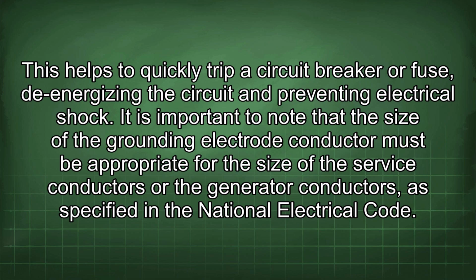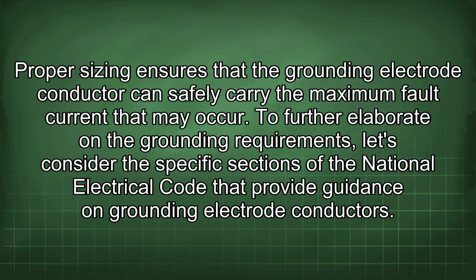It is important to note that the size of the grounding electrode conductor must be appropriate for the size of the service conductors or the generator conductors, as specified in the National Electrical Code. Proper sizing ensures that the grounding electrode conductor can safely carry the maximum fault current that may occur. To further elaborate on the grounding requirements, let's consider the specific sections of the National Electrical Code that provide guidance on grounding electrode conductors.